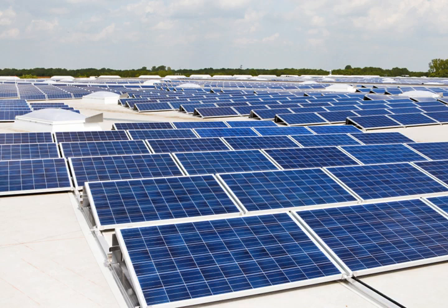Micro-inverted solar panels are wired in parallel, which produces more output than normal panels which are wired in series, with the output of the series determined by the lowest performing panel. This is known as the Christmas light effect. Microinverters work independently, so each panel contributes its maximum possible output given the available sunlight.